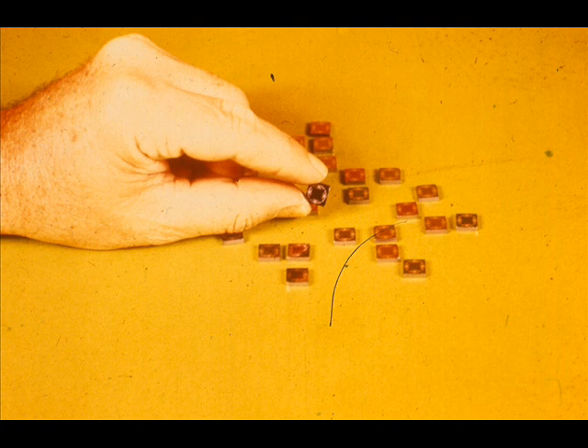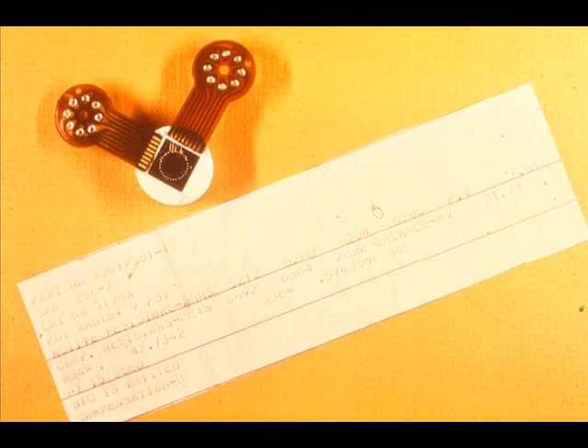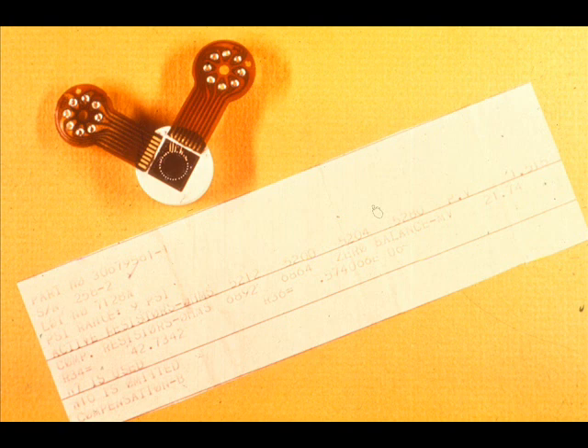The piezo-resistive strain gauge serves as the differential pressure detector. It is a fully active Wheatstone bridge that is diffused into a single crystal of silicon. It is not the typical bonded strain gauge that stretches and changes configuration during stress. The piezo-resistive strain gauge is a solid state device, much the same as a transistor or a diode.